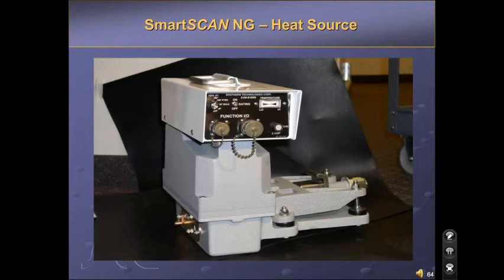The power cord from the heat source should be toward the front of the scanner to indicate the heat source is mounted correctly. The NG heat source has a bracket mounted to the bottom of the unit that will allow the heat source to set directly on top of the scanner. To place on the scanner, slide the heat source from the back of the scanner forward until it stops. This will provide correct placement of the heat source. The scanner is now ready for calibration.